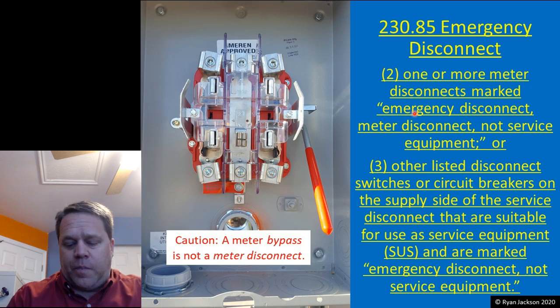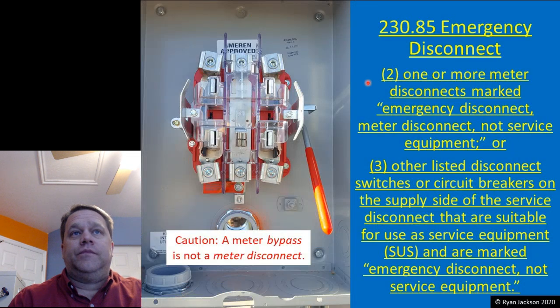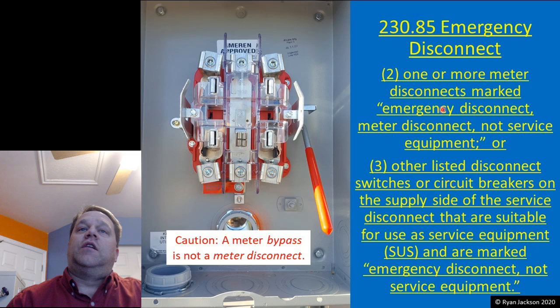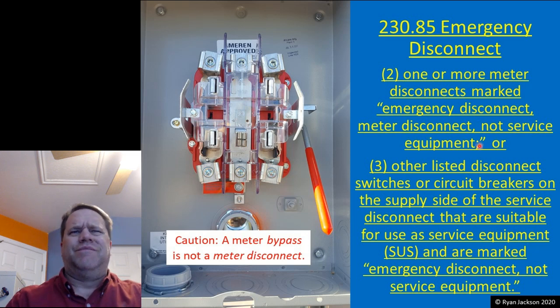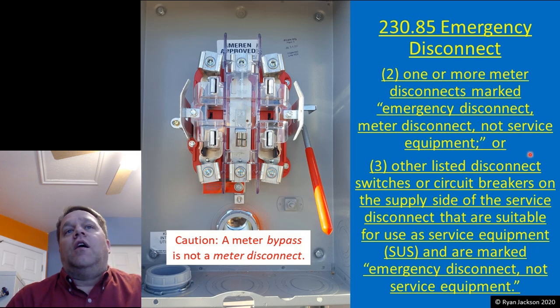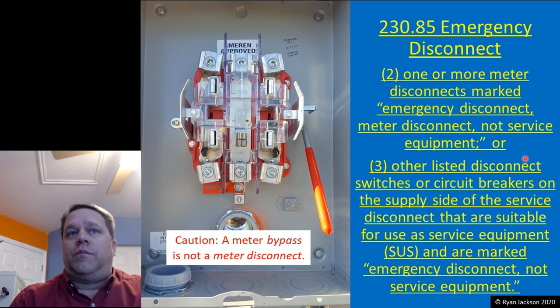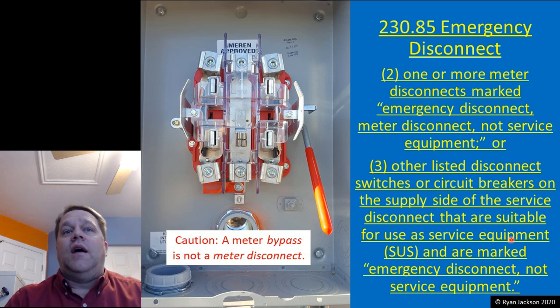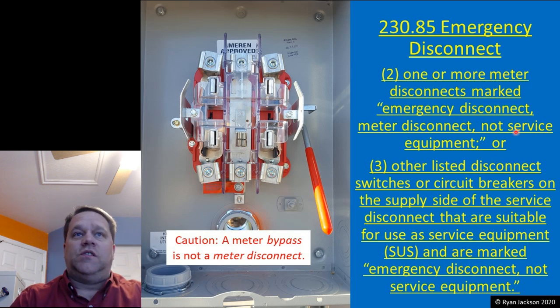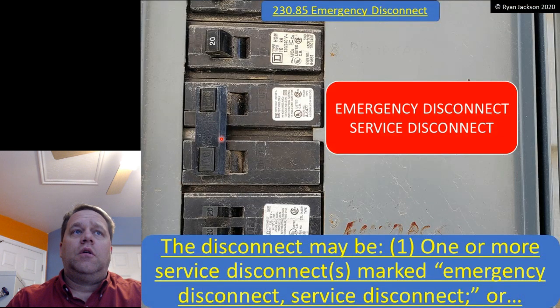So what else can I use? I can use the service disconnect, or I can use one or more meter disconnects that are marked emergency disconnect, meter disconnect, not service equipment. It's a mouthful. Or item three, other listed disconnect switches or circuit breakers on the supply side of the service disconnect that are suitable for use as service equipment and are marked emergency disconnect, not service equipment. So again, I think the option that you're going to be seeing in most applications is a panel board with a single service disconnect in it. Shut it off. That's your emergency disconnect.